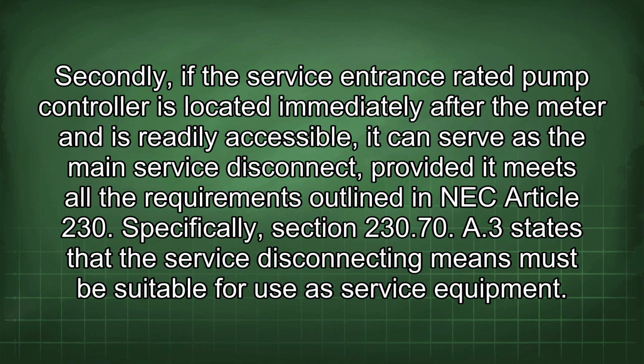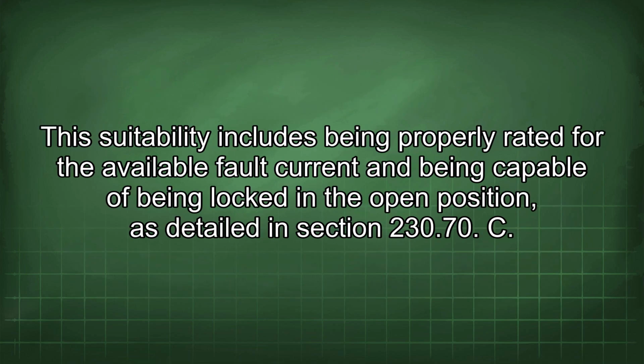Secondly, if the service entrance rated pump controller is located immediately after the meter and is readily accessible, it can serve as the main service disconnect, provided it meets all the requirements outlined in NEC Article 230. Specifically, Section 230.70(A)(3) states that the service disconnecting means must be suitable for use as service equipment. This suitability includes being properly rated for the available fault current and being capable of being locked in the open position, as detailed in Section 230.70(C).